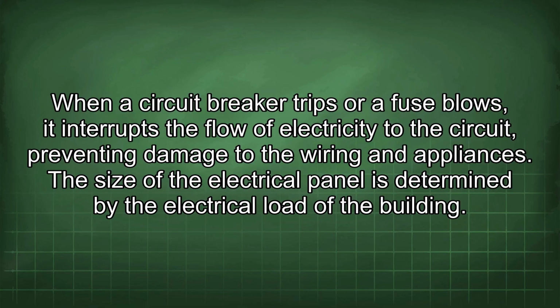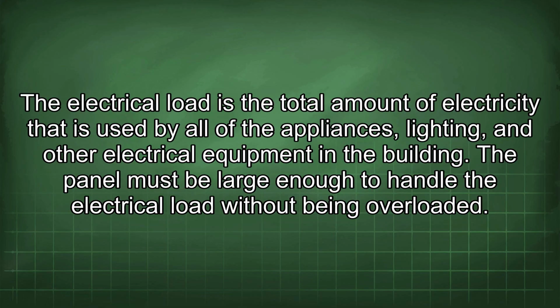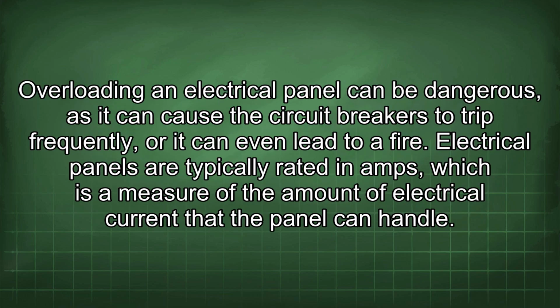The size of the electrical panel is determined by the electrical load of the building. The electrical load is the total amount of electricity that is used by all of the appliances, lighting, and other electrical equipment in the building. The panel must be large enough to handle the electrical load without being overloaded. Overloading an electrical panel can be dangerous, as it can cause the circuit breakers to trip frequently, or it can even lead to a fire.